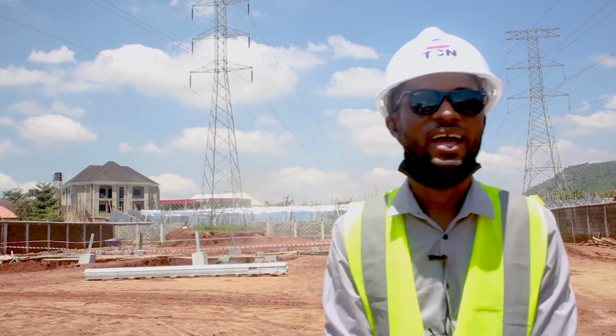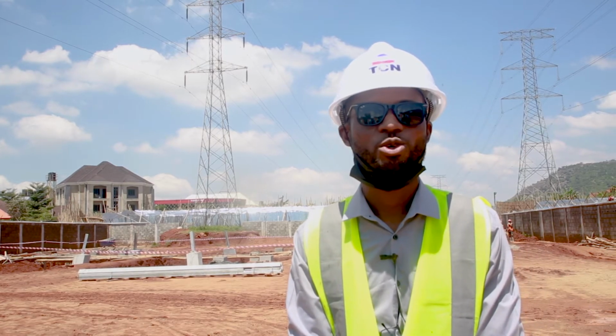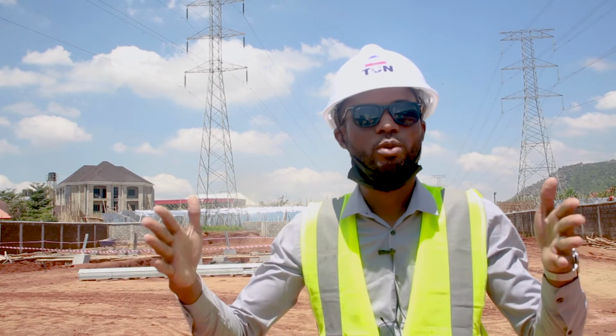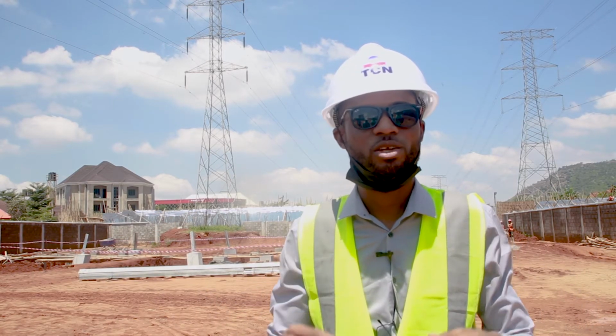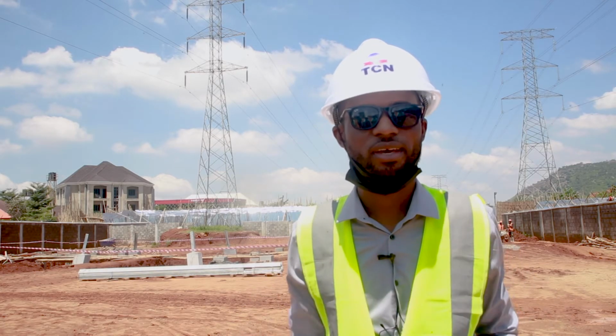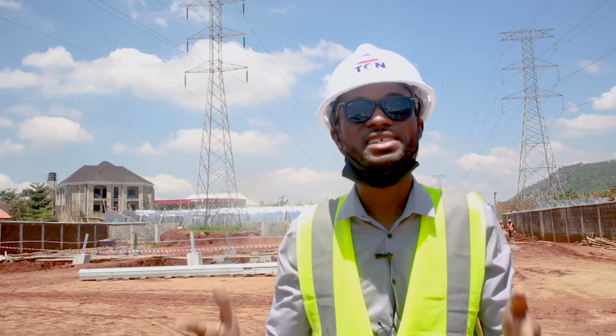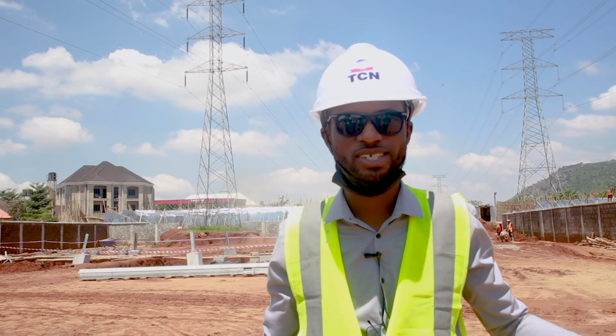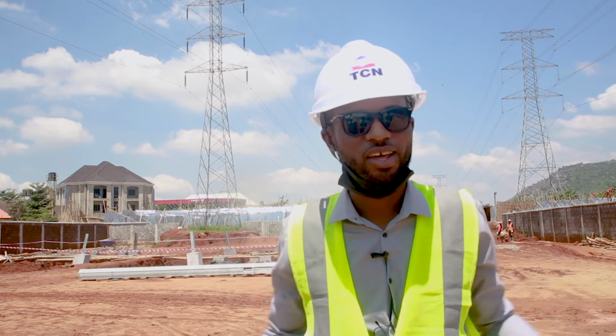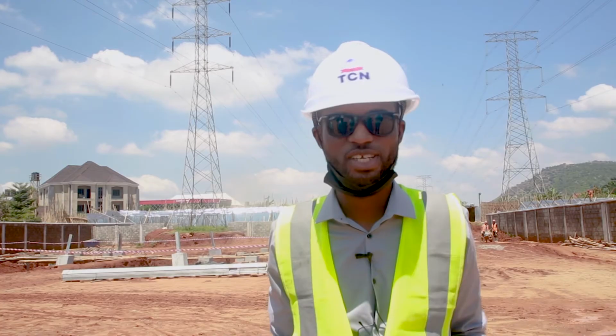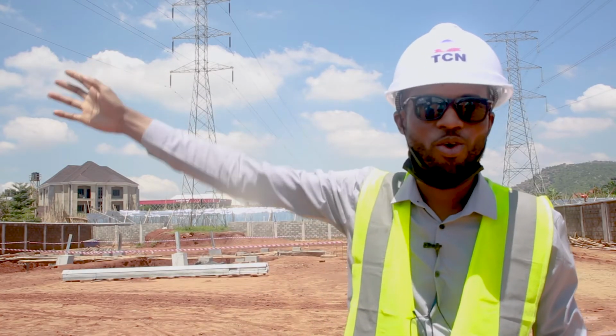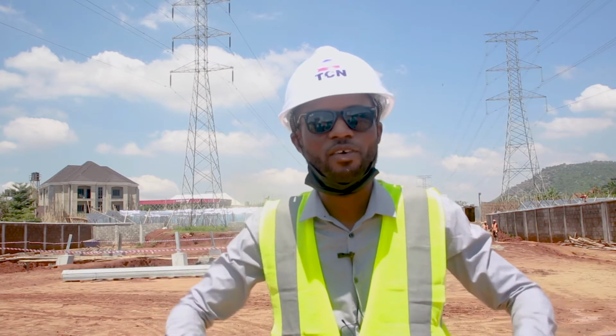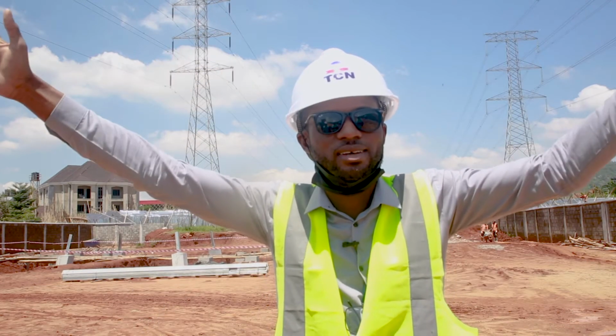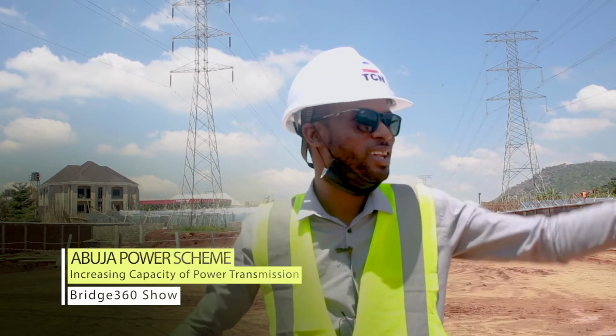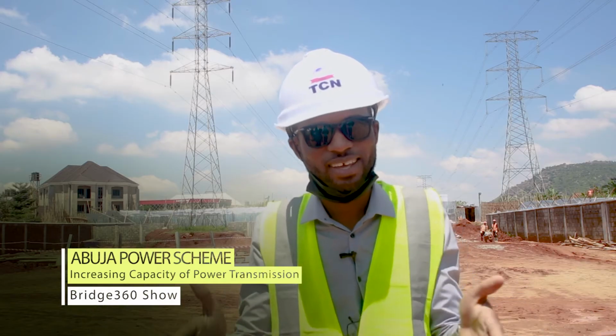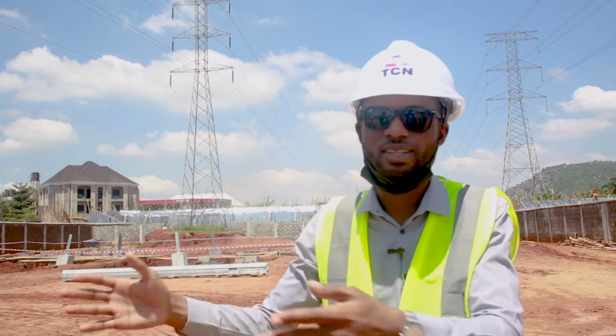What we used to have is AIS, air insulated switchgear. Due to space constraint, we adopted a new technology called GIS, gas insulated switchgear. This gas insulated switchgear consumes less space than what you see at a typical AIS site. Most of our substations are built on the outskirts of towns where we have ample space for gantries and bus bars, while this one is in the middle of communities where space is very limited, so we adopted this technology here.